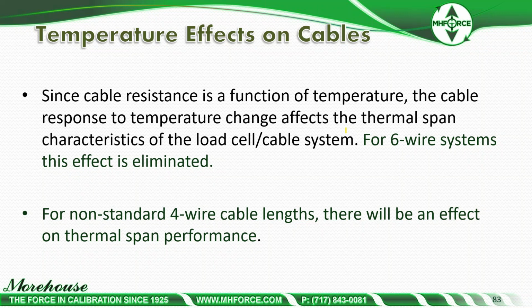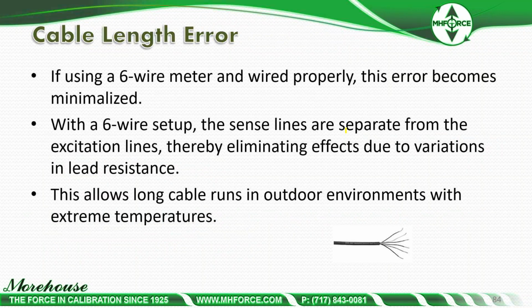It's going to be like 0.01, and it all depends on the gauge. Most things I've seen is about 0.01 per every 10 feet. For every 10 feet, that would be the absolute best I've seen. A 0.01% change for every 10 feet would be the best cabling change I've seen, and that's usually the really thick ones. If using a 6-wire meter wired properly, this error becomes minimalized. With a 6-wire setup, the sense lines are separate from the excitation lines, thereby eliminating effects due to variations in lead resistance.